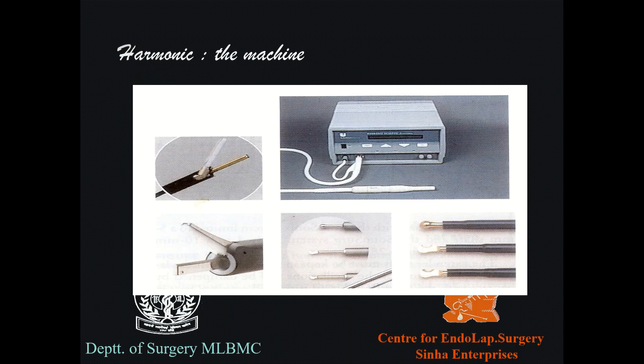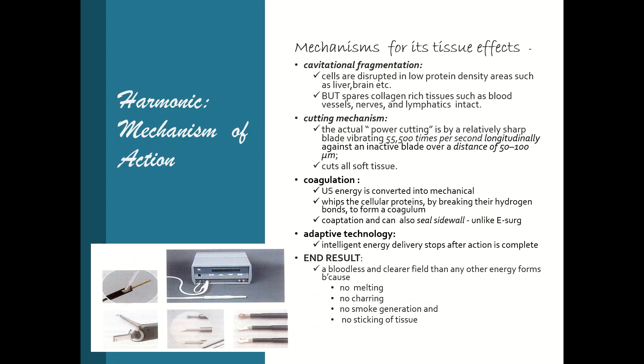This is the Harmonic machine — the generator, the piezoelectric crystal, the handpiece, and the attachments through which energy is delivered to tissue. The first mechanism of tissue effect is cavitational fragmentation: cells are disrupted in low protein density areas such as liver and brain, but it spares collagenous tissue like blood vessels, nerves, and lymphatics, making it a much less bloody kind of dissection.